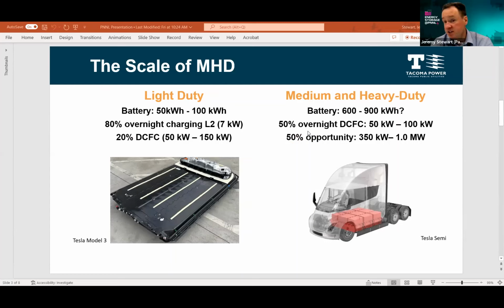Comparing to medium and heavy duty, the batteries are much larger - 600 to 900 kilowatt-hours, maybe more. About 50% is estimated to need some type of overnight DCFC in the 50 to 100 kilowatt range, so your average overnight charge size is larger. Plus there's a lot of opportunity charging, ranging anywhere from 350 kilowatts to 1 megawatt. It's a very different scale, moving from something like a water heater or residential dryer load into an industrial load classification. Figuring out how we integrate these things is an interesting challenge.